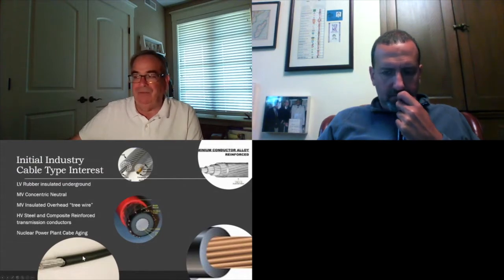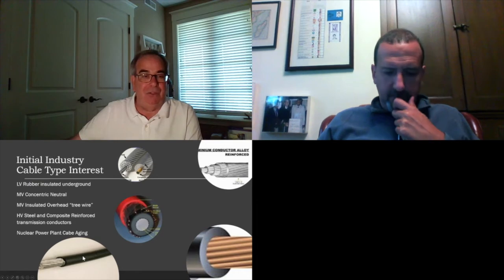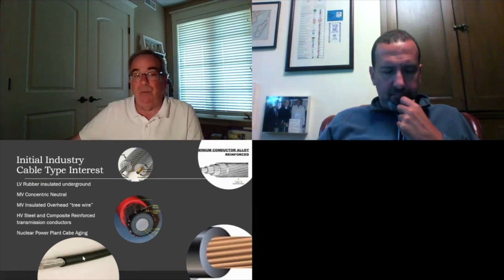So these are some of the types of cables that we're testing. Like I said, the one on the right, the lower right, is the type of cable that would be used in an underground low voltage network. The one left of that is a medium voltage overhead cable that might operate anywhere from 4 kV to 35 kV, and it's called tree wire because it has a rubber coating on it, or some material coating, that prevents trees from touching it and causing a fault.